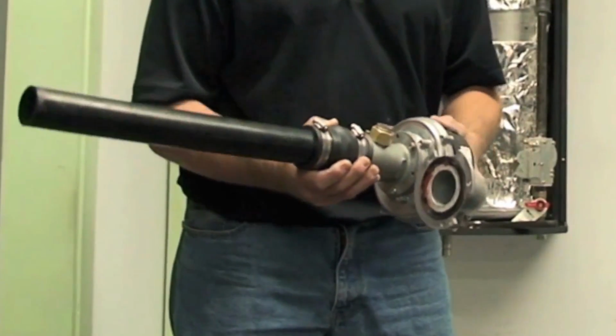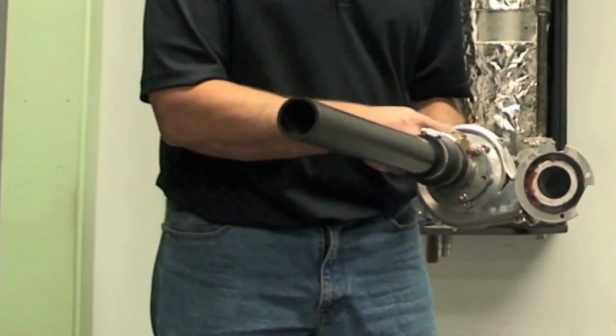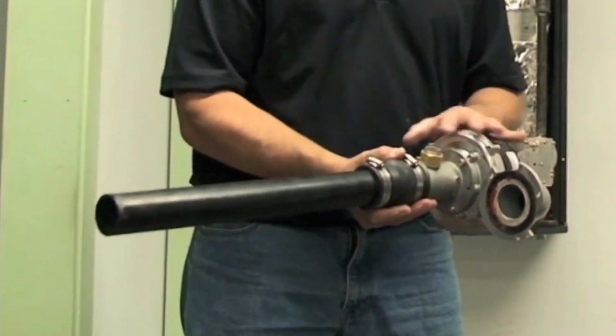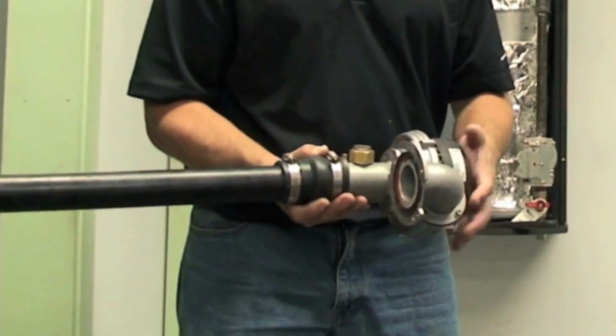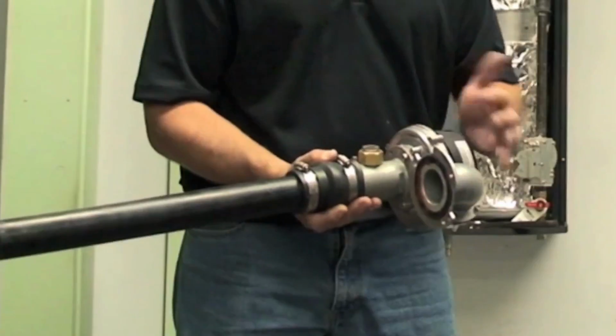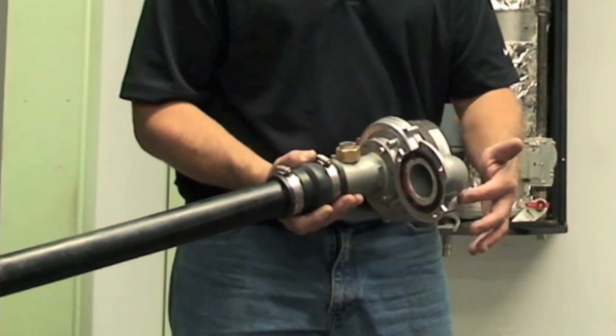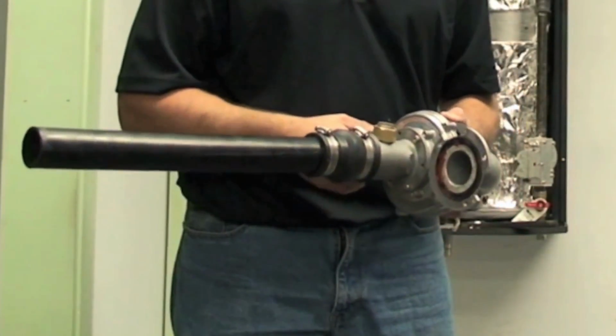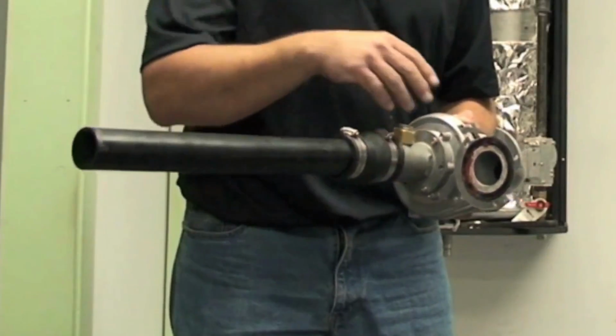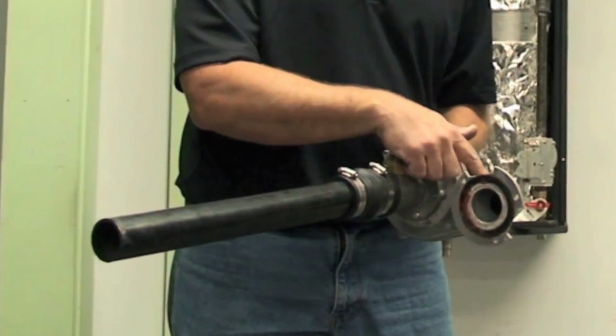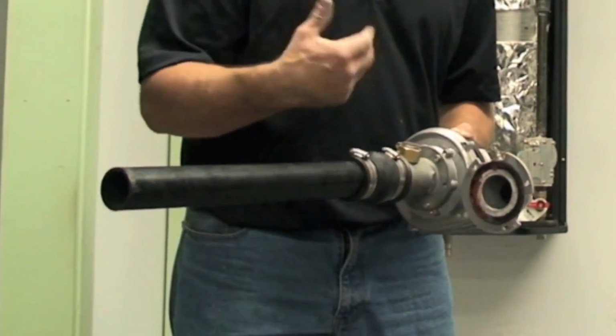And the venturi can come off with these 4 screws here. And the blower outlet, if you need to change the channel or you need to change the blower, you just disconnect these 2 screws, put the new blower on, secure your venturi, secure your blower outlet, and you're done.